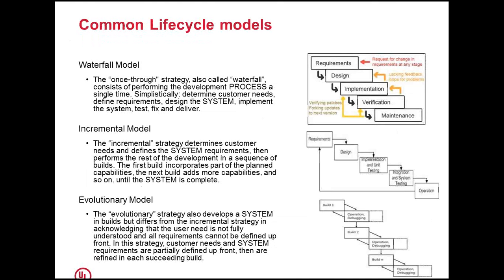The common life cycle models used across the industry, specifically for medical devices, are the waterfall model, incremental model, and evolutionary model. There are a lot of write-ups freely available on the web on these models, and which is good, which is bad. It all depends on the situation in which the development is happening and the requirements.